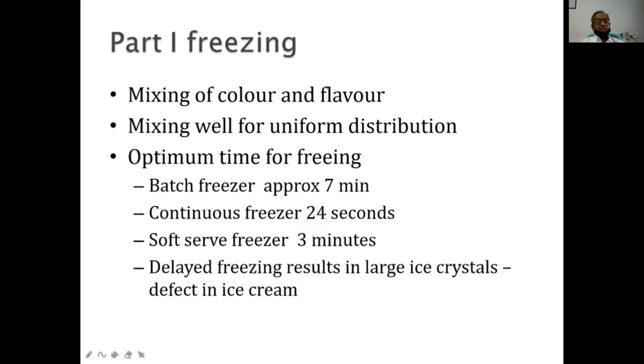Softy ice cream we have also seen; it is similar to the batch process. In that we put in the mix and it requires 3 to 4 minutes to come out as partially frozen ice cream. If you take more time, what is the difference in the process? Now, what are the advantages and disadvantages? I will not go into much detail, but as a refrigeration engineer I will explain that if we take more freezing time, the ice crystals will become bigger and bigger, and that is a defect in the ice cream. Slow freezing gives bigger crystals and gives the mouthfeel of ice, not ice cream. The larger crystal is a defect in ice cream, so fast freezing is recommended and desirable.